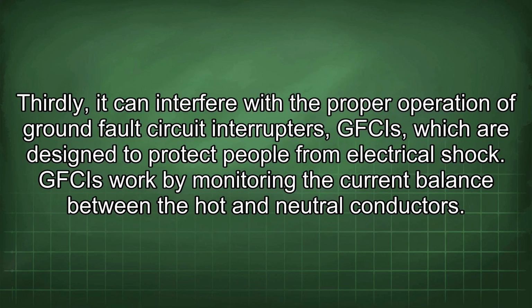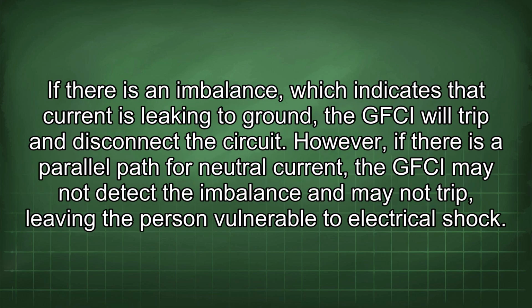Thirdly, it can interfere with the proper operation of ground fault circuit interrupters, GFCIs, which are designed to protect people from electrical shock. GFCIs work by monitoring the current balance between the hot and neutral conductors. If there is an imbalance, which indicates that current is leaking to ground, the GFCI will trip and disconnect the circuit. However, if there is a parallel path for neutral current, the GFCI may not detect the imbalance and may not trip, leaving the person vulnerable to electrical shock.